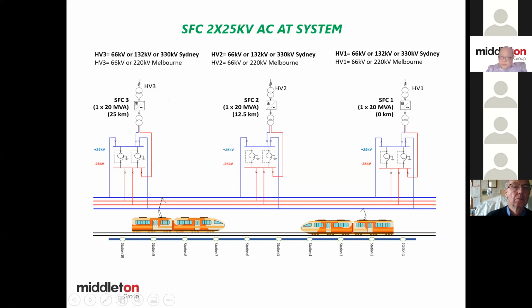If we were to use static frequency converter for the example that I've shown you earlier, as a very minimum, you will need 3 units, spaced almost equally like this. That means to operate the railway, you will most certainly need 2 of them running to be able to provide the service you require. If necessary, you can always add another unit, which is quite handy. So whether you put it in here and here, or you double up on the same side, depends on whether you are able to get another independent HV supply or not for your N-1 redundancy. So on the railway side, if it's a 25 kV system, you don't change anything. It's the same, except that there are no neutral sections.